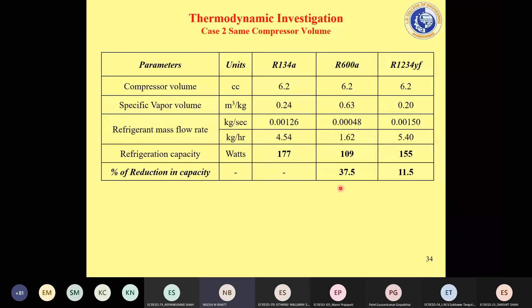So if we conclude the thermodynamic investigation, we can say that the COP reduces by 7.22% and 8.33% respectively for YF and R600A, but the compressor size increase is just 4.9%, about 5%, for R1234YF, while the compressor size is almost 1.5 or 1.6 times higher for R600. So that is a major change, a major requirement of compressor change in case of R600A, if you want to use R600A.